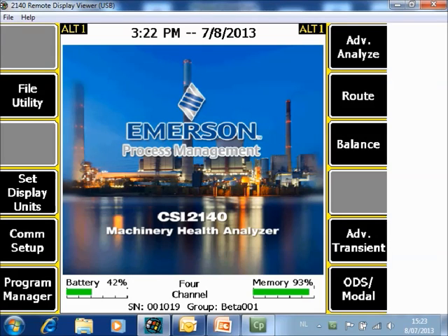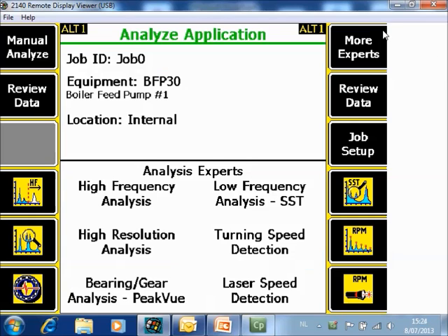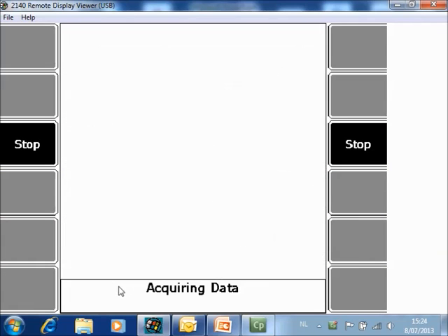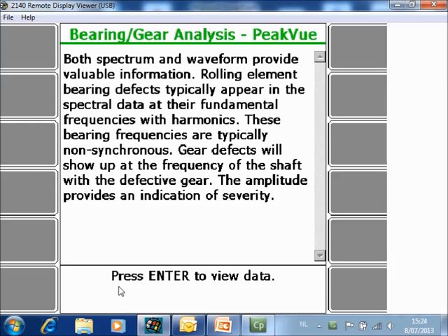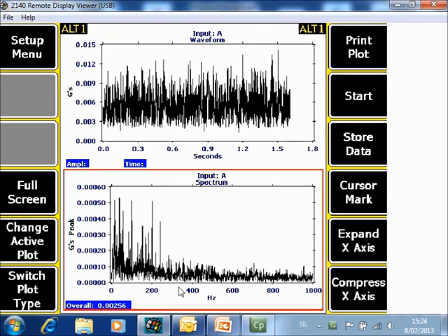These PeakVue measurements can also be collected in the job mode. From the home screen of the CSI 2140 Machinery Health Analyzer, go to F7 Analyze, then F6 Bearing Gear Analysis PeakVue, and start data collection. After collecting the data, press Enter to view. A spectrum and a waveform up to 1000 Hz with PeakVue technology is measured, and it can be stored in the job mode by pushing F9 Store Data.